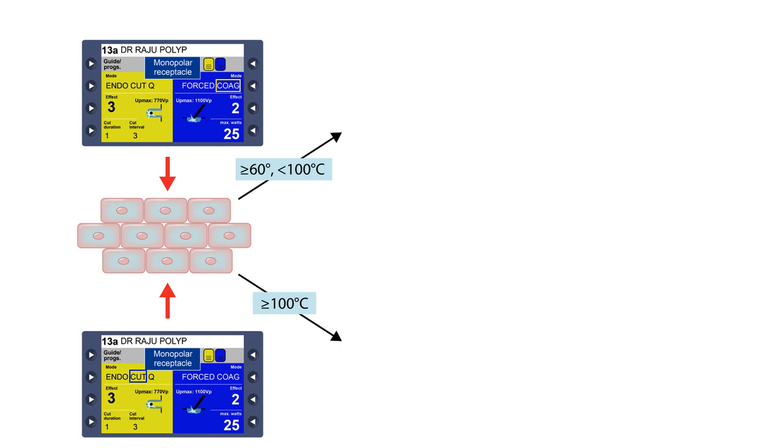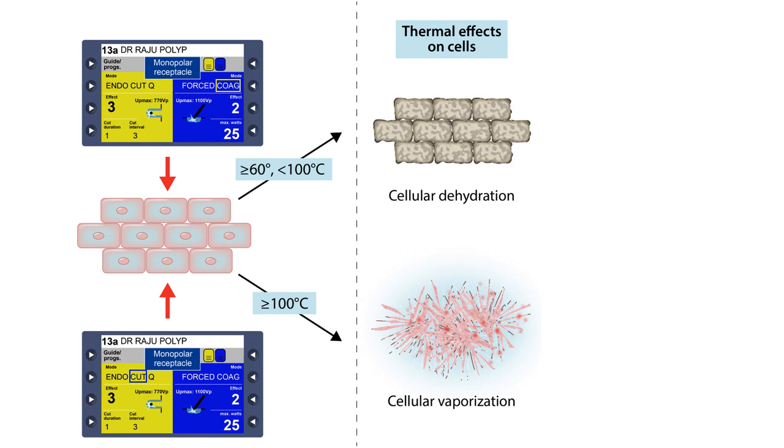For coagulation, it is between 60 to 100 degrees. For cut, it has to be above 100 degrees for the water in the cells to boil. It is not only the temperature elevation, but also how fast it actually happens.